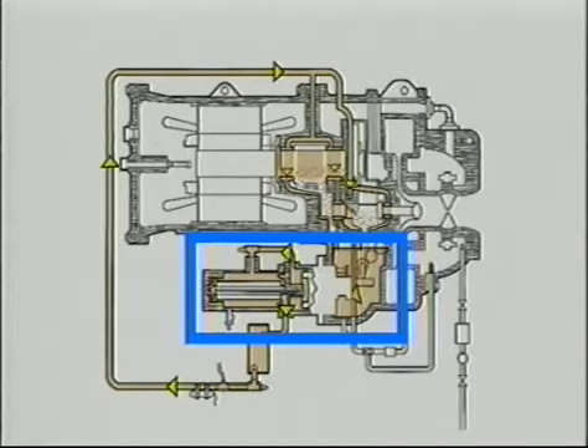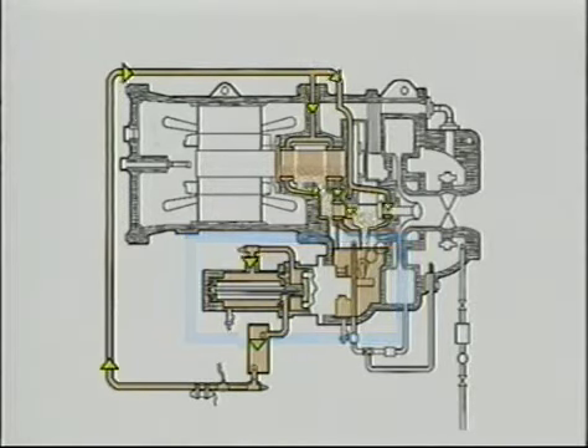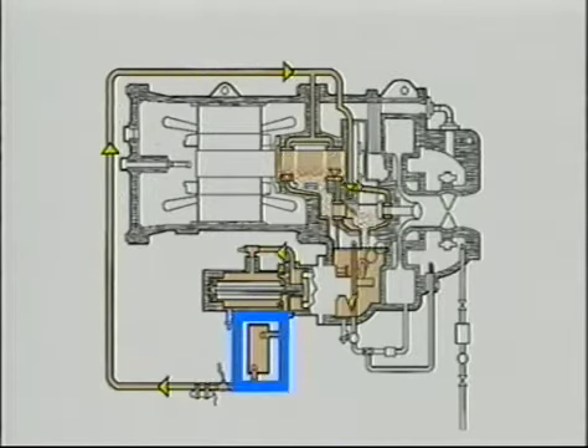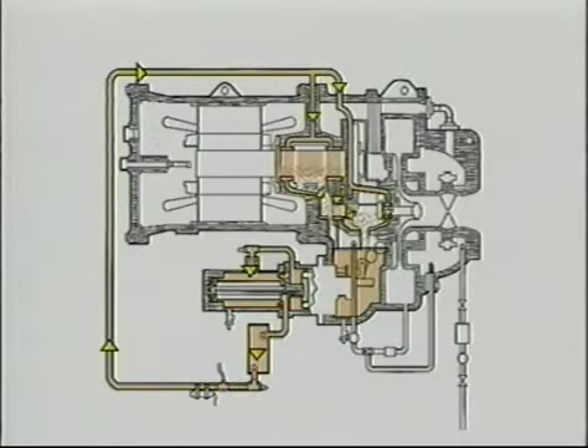Pressurized oil then passes from the pump motor housing and into the filter chamber via some external piping. After being filtered, the oil is piped to the external oil cooler. The pressurized oil flows to the transmission assembly where it feeds two lines. One line supplies oil to the high-speed thrust-bearing assembly and lubricates the gears. The other line supplies the low-speed shaft bearings. From there, the oil is channeled to the high-speed shaft bearing nearest the pinion. The oil then drains to a sump at the base of the compressor housing.